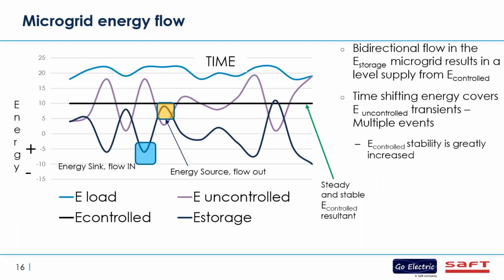This next graph shows all of the different energy terms graphically. So you have load, you have a controlled source, and uncontrolled, and the balancing of the storage system. The bidirectional flow in the storage microgrid results in a level supply from the controlled energy. It helps base load it, and it slows the required system response back down to controllable time frames.